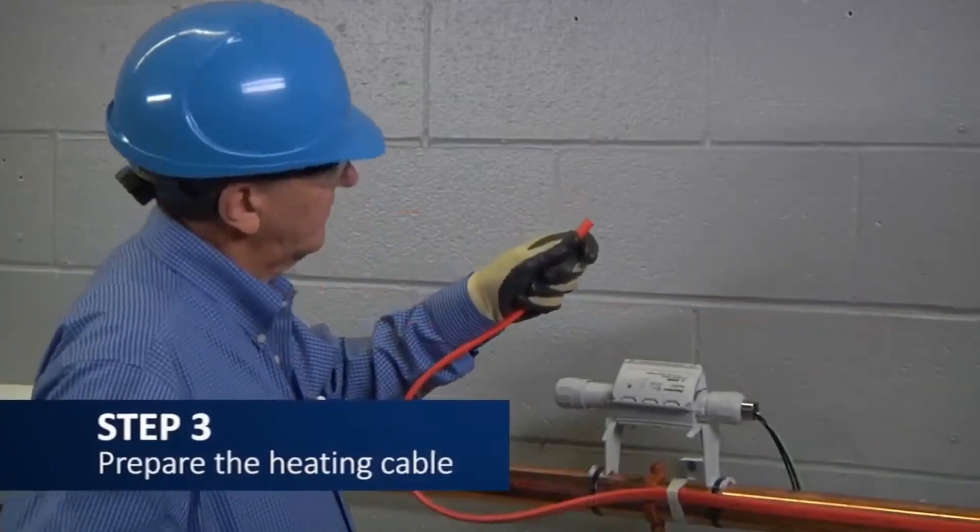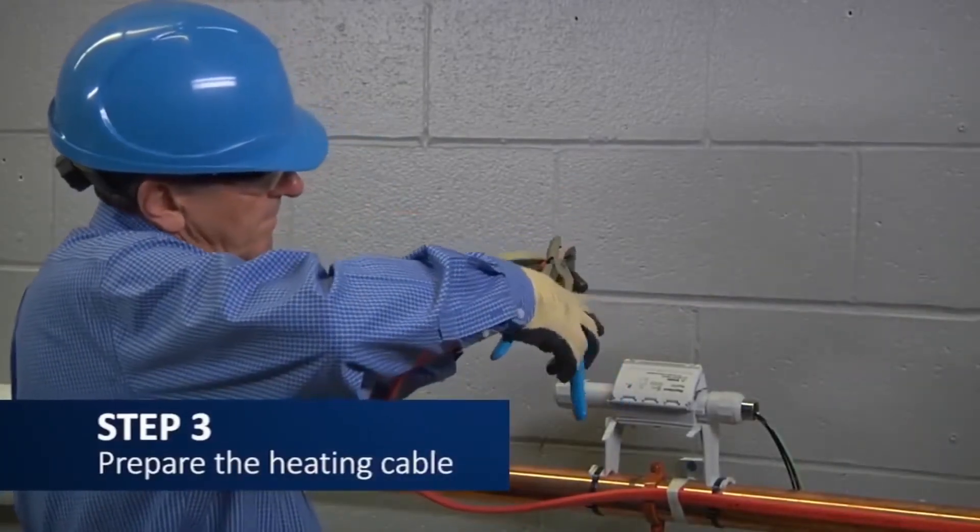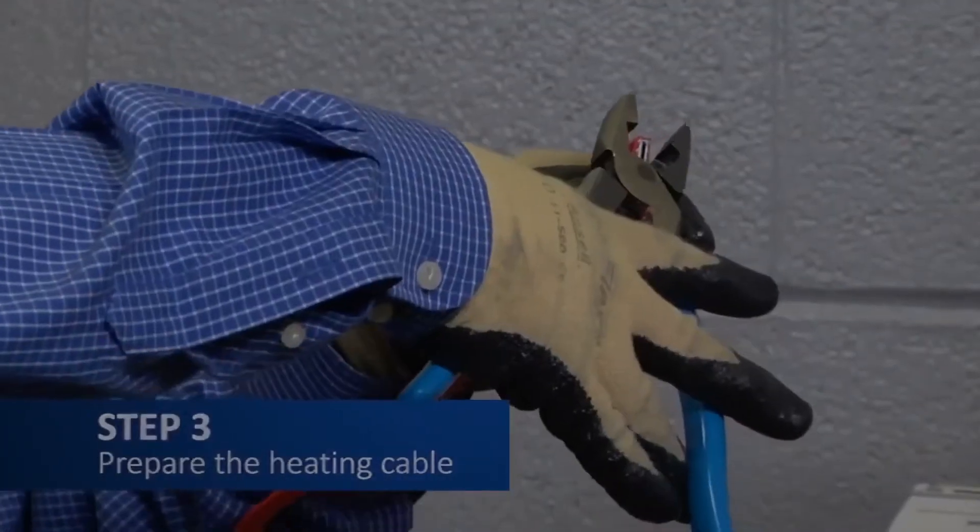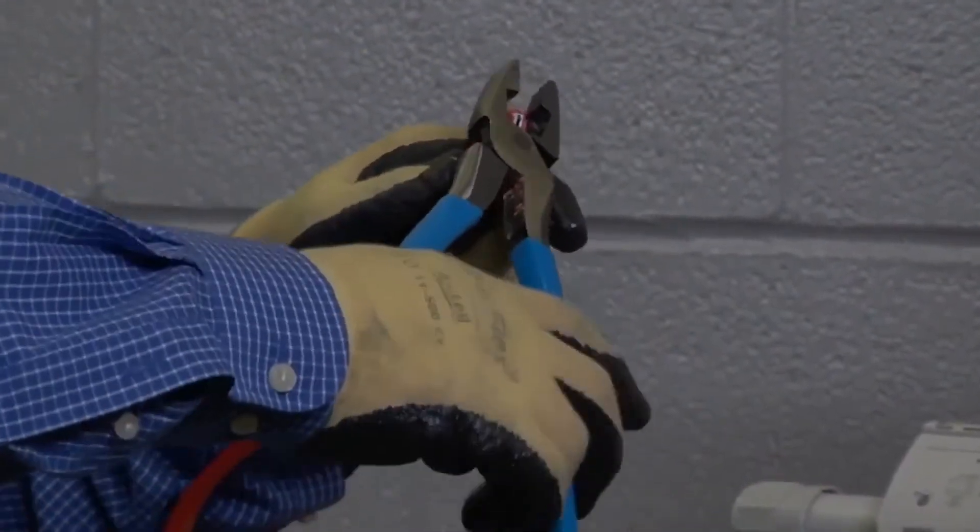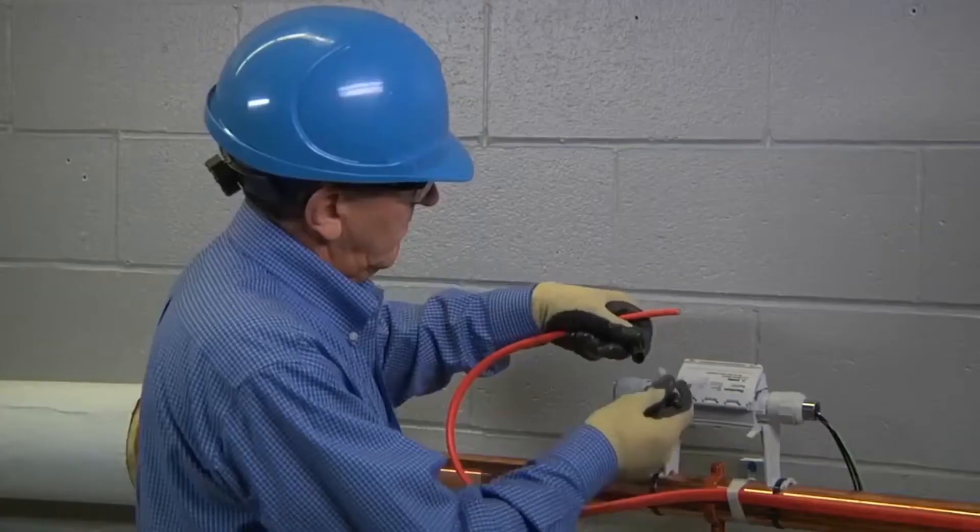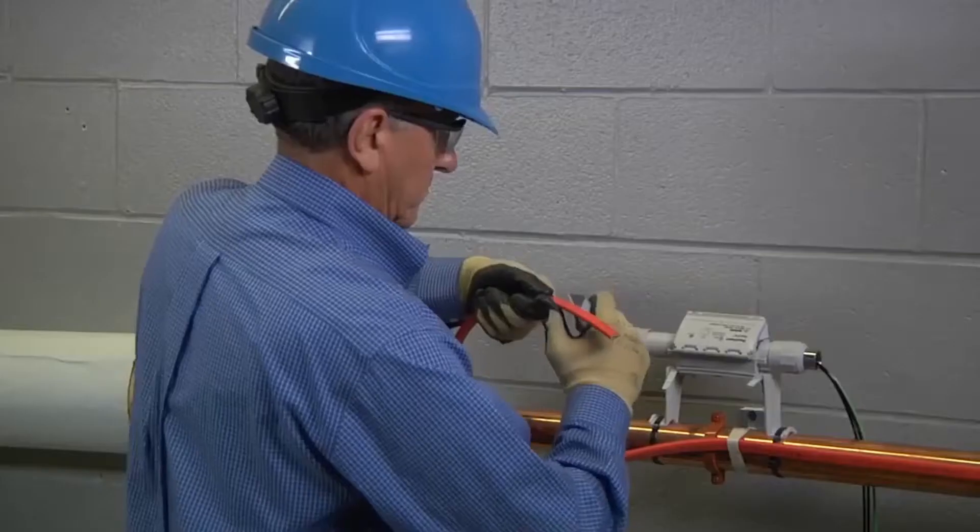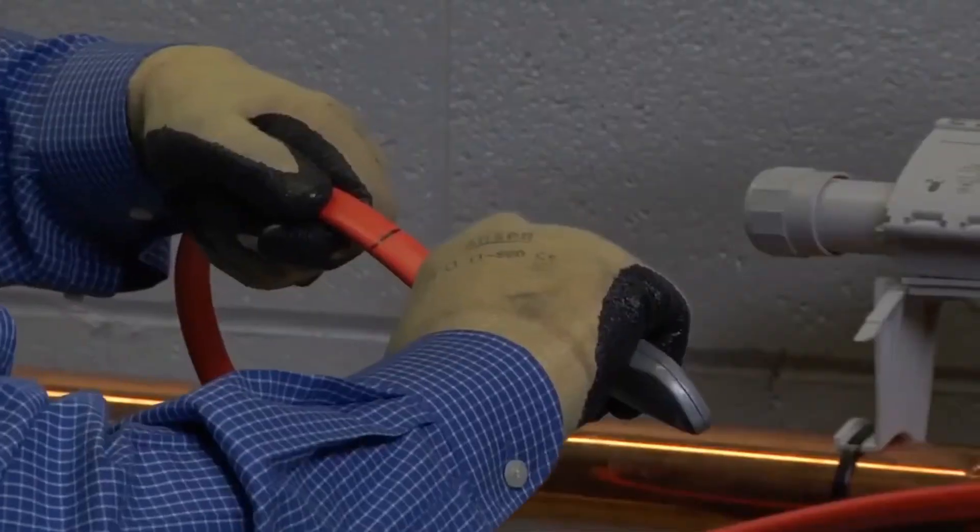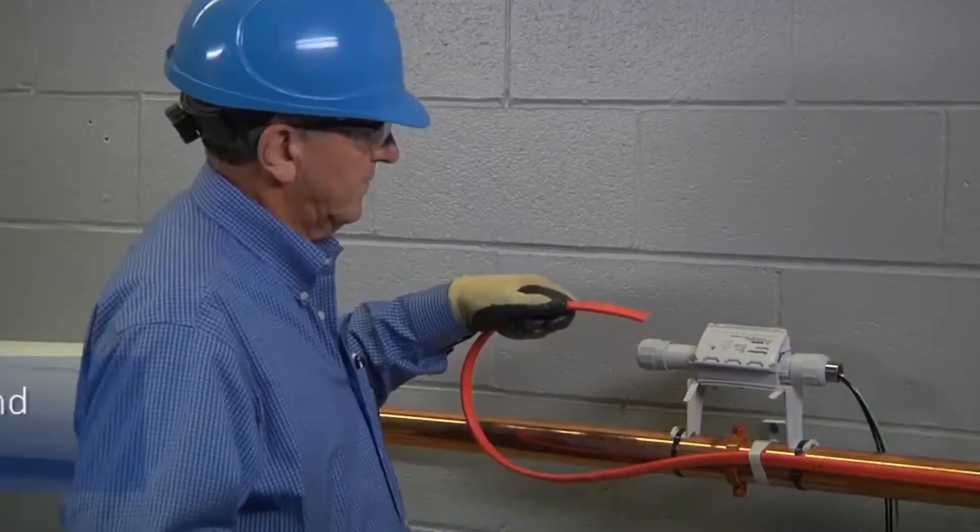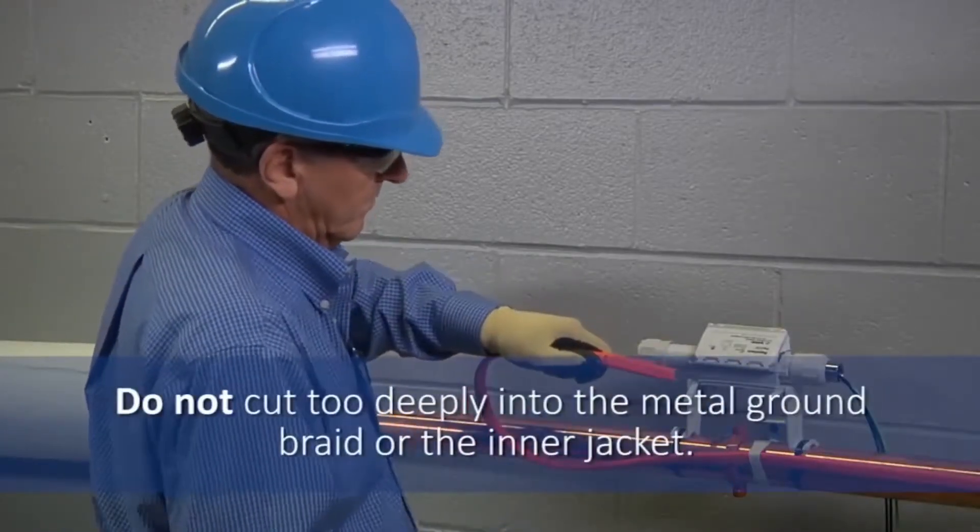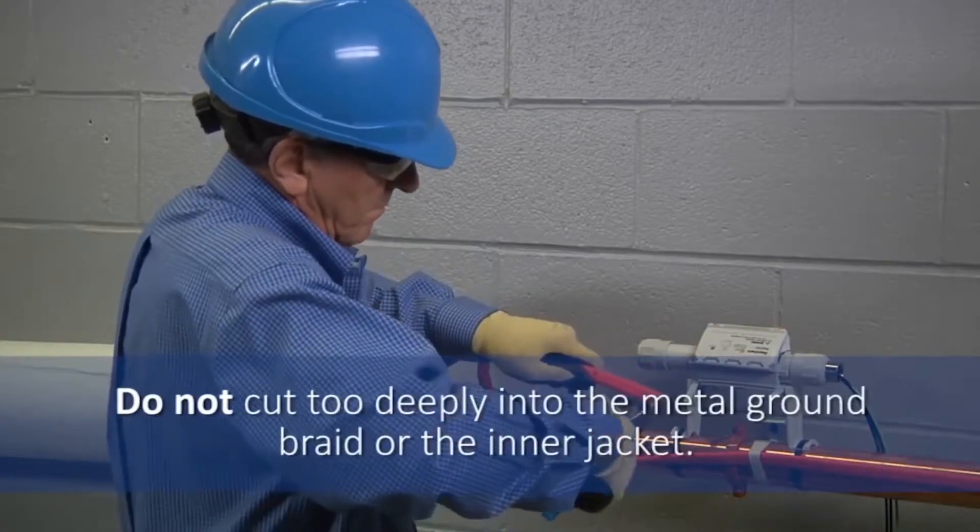Now, to install the RayClick, take the end of your heating cable to be connected - HWAT in this case - and cut the end square with your wire cutters. Place a mark three and one-eighths of an inch from the end of the cable, and score around and down the middle towards the end of the cable, being careful not to cut too deeply into the metal ground braid or the inner jacket.